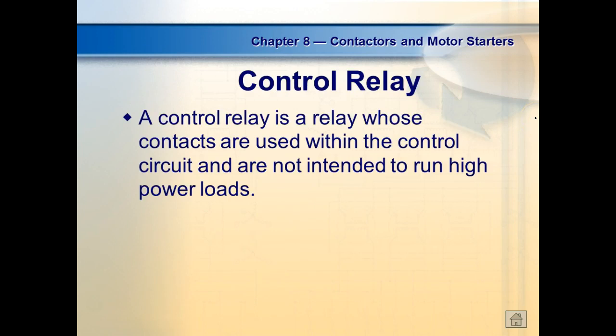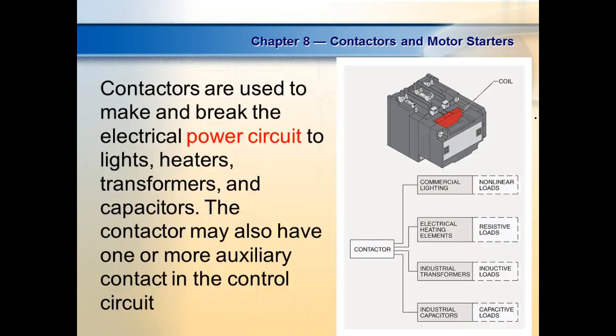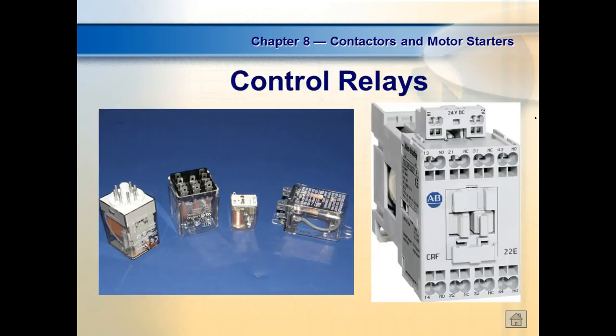A control relay is a relay whose contacts are used within the control circuit and are not intended to run high power loads. All these things are intended to do is run other relay coils, run small lights, not big lights, small lights, maybe solenoids, and little fractional horsepower motors. And so these are some of the control relays.